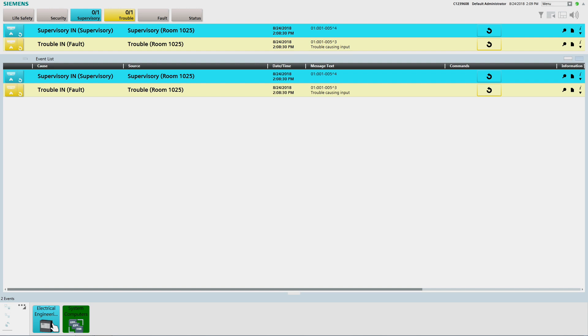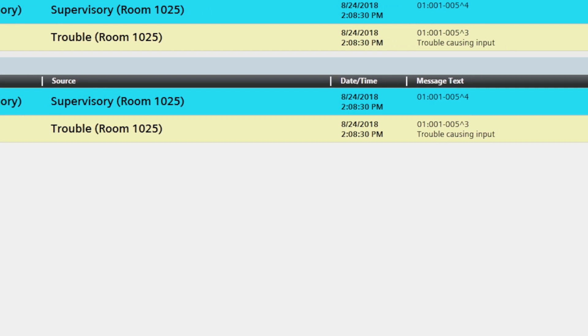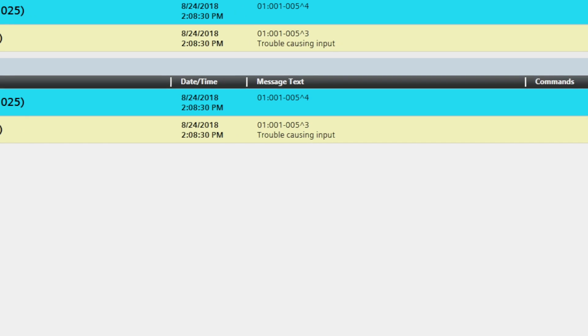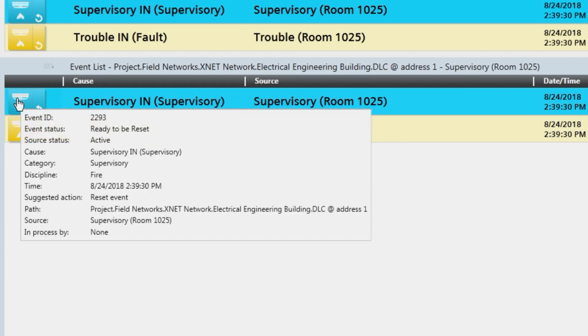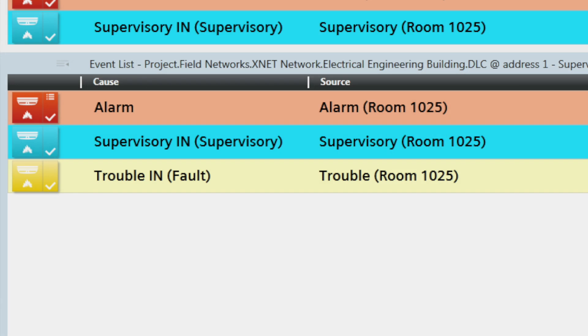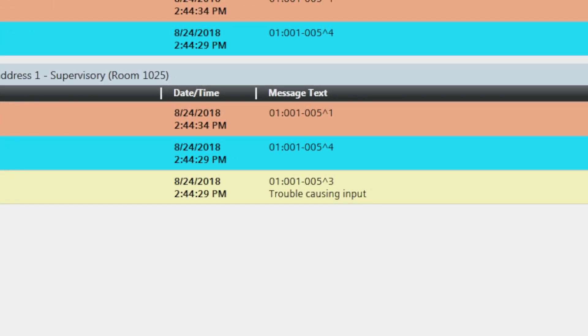Next, we have the event list, which is always located below the summary bar. The event list displays all active events on the connected panels and contains a row for each event with several columns of information. Starting on the left-hand side, there is an event icon that graphically summarizes the most important information about the event. By hovering the mouse cursor over the event icon, additional information is displayed in a tooltip box. The event button will flash and the audio buzzer will sound until the event is acknowledged. The next column is the event cause column, which provides a textual description of the event cause. Then we have the source column, which indicates the physical location of the device where the event is occurring. To the right is the date and time column, followed by the message text column, which provides more detailed information about the event cause.